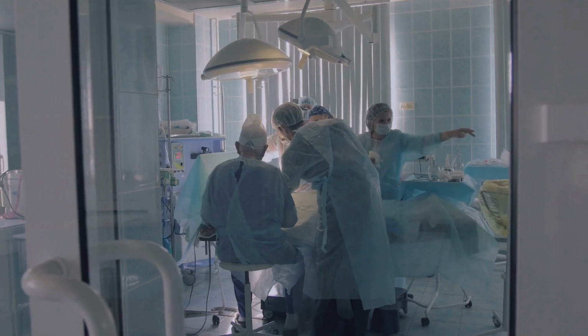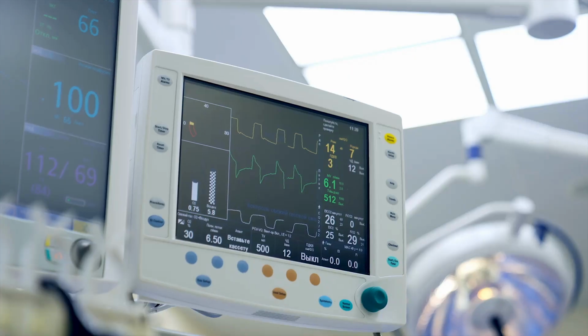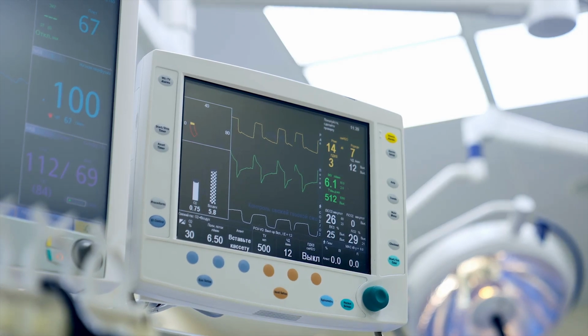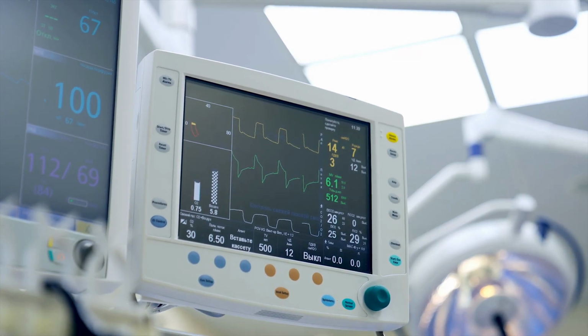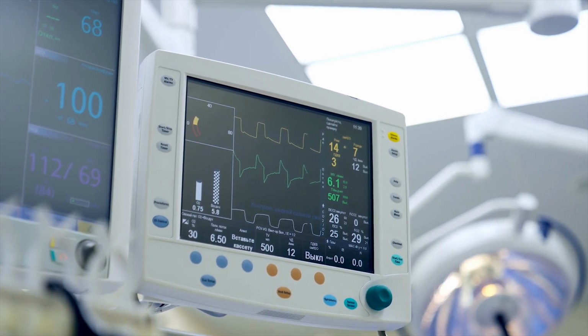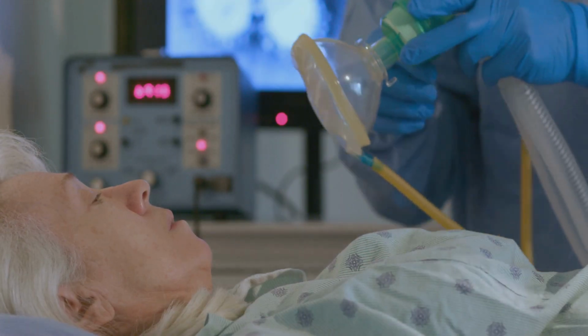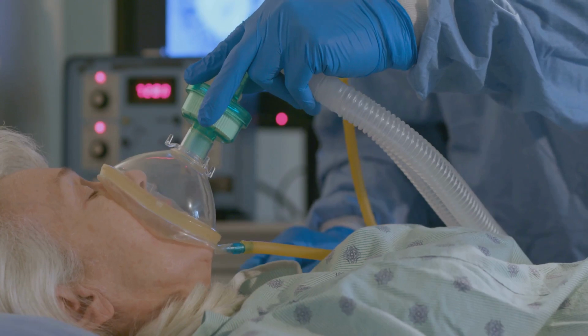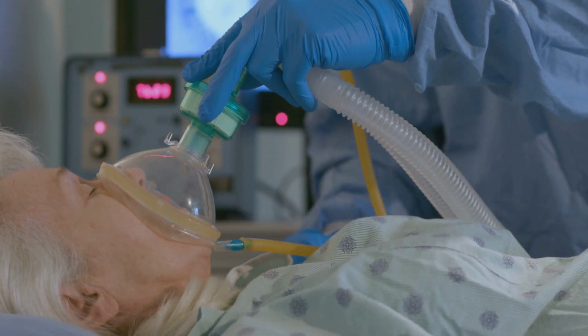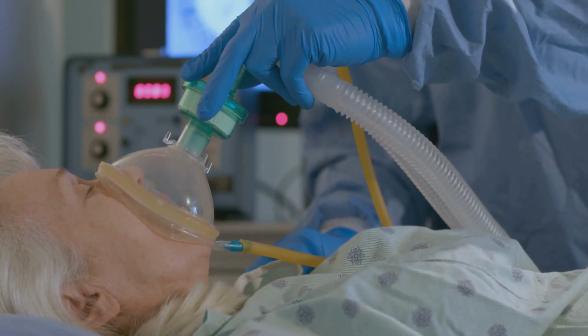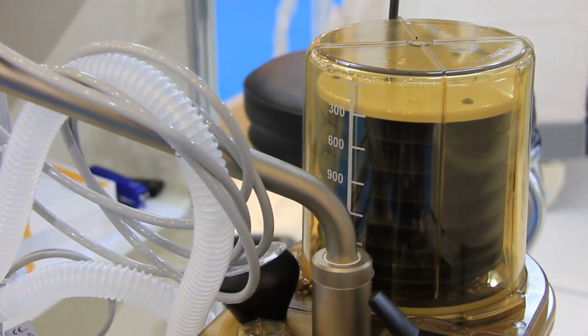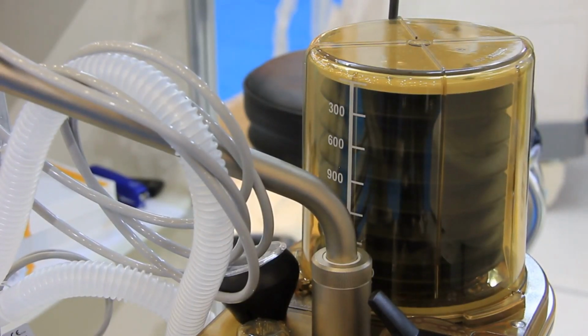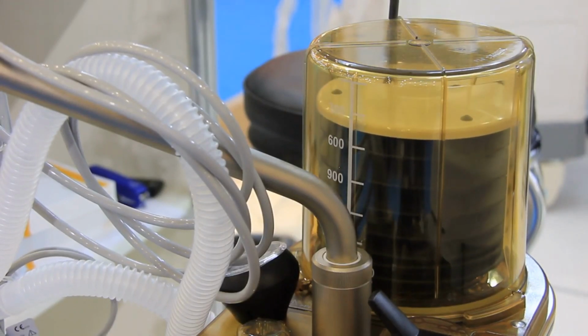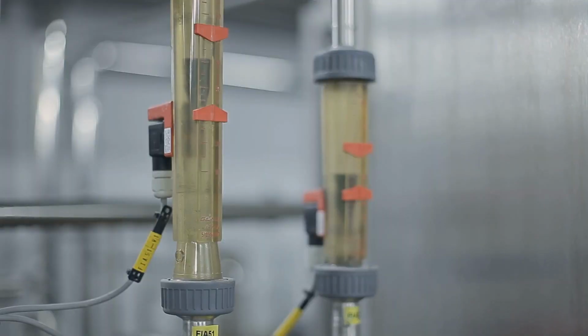This is where the anesthetic gas scavenging system comes into play. Operating like a vigilant guardian, the scavenging system captures these escaped gases before they have a chance to contaminate the environment. It does this by connecting to the anesthesia machine's patient breathing circuit. Any excess gases that aren't metabolized by the patient are captured and redirected away from the patient and the healthcare team. But where do these gases go? The scavenging system, true to its name, scavenges these gases, channeling them into a disposal assembly. This assembly typically consists of two main parts: a reservoir to hold the gases momentarily, and a vent to release them safely out of the building and into the outside air.